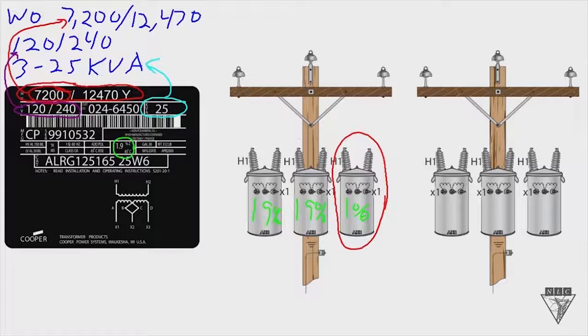Because remember when I said when you think of impedance, think of resistance. Well, if it's got less resistance, then it's going to take on more of that load, which could overload that transformer and make it fail. So you want to try and find 3 transformers that have impedance that are very close together. Some companies will give it a plus or minus 5% range, but check with your company just to find out what they require.